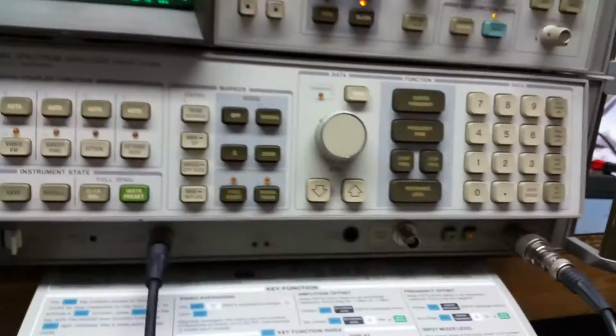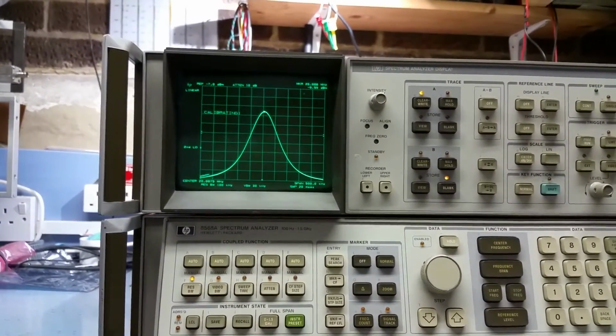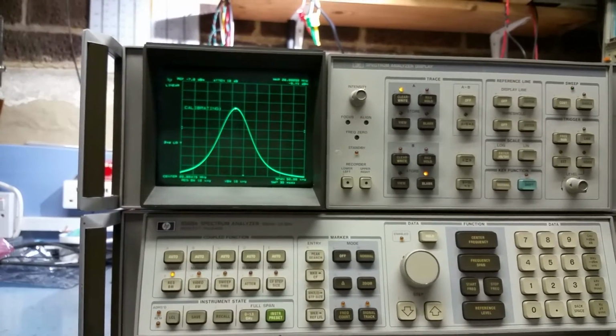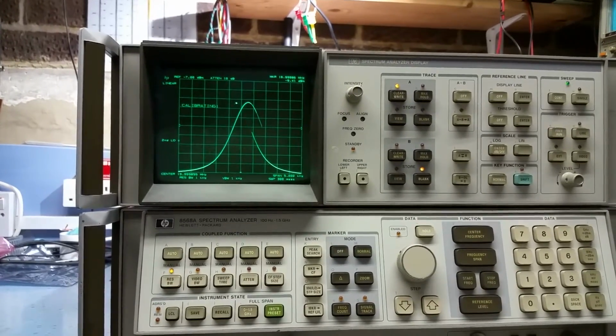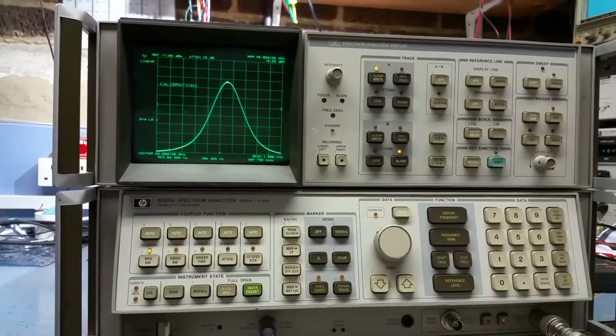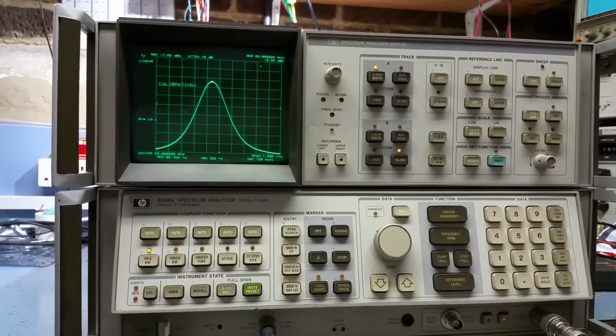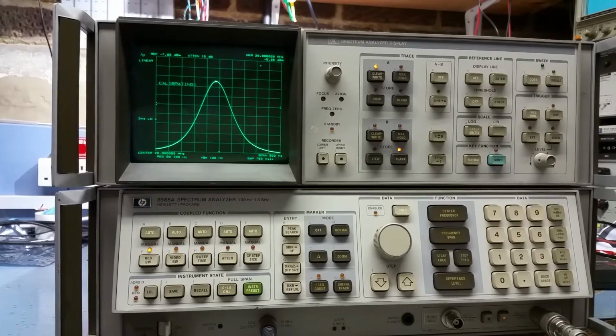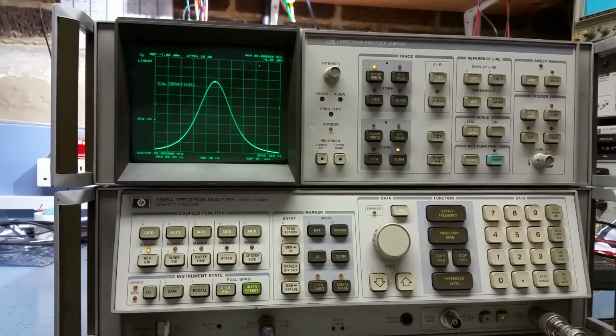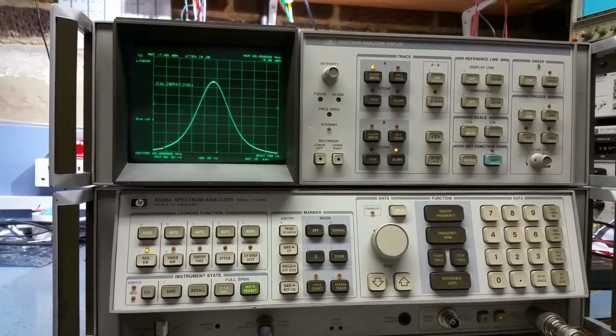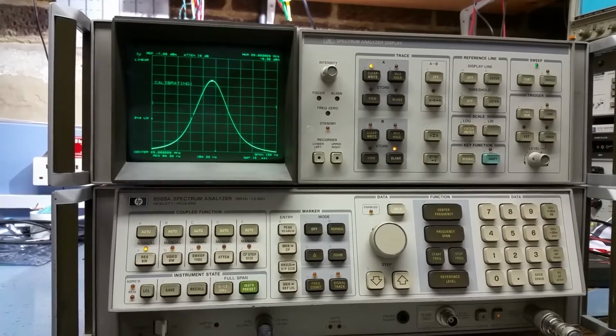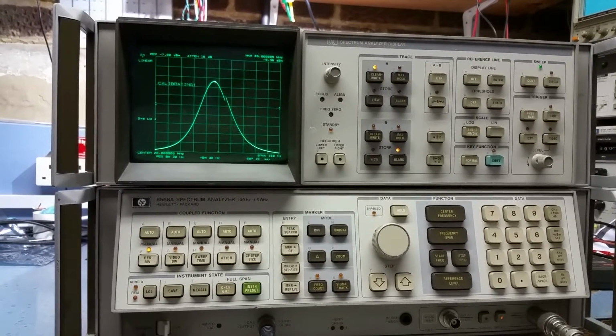And then what we do is we run the error correction routine, and that's shifted function and W. Now it's the capital W, not the lowercase w, which I kept pressing before and thinking, why isn't this working? And it runs the calibration procedure you saw previously. Takes about a minute to run. Running a lower sweep.